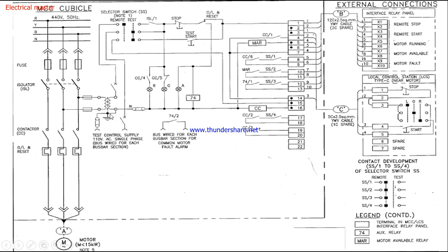One secondary winding is connected to grounding, so that line becomes the neutral line. I connected it to the neutral link, and the phase line is connected to the control MCB. When I turn on the MCB, power supply connects to the selector switch — as I showed in that cubicle diagram. Whenever the remote position is selected, the power supply goes in this way. There is one interlock here: whenever the main isolator is closed, only then do we receive power here.